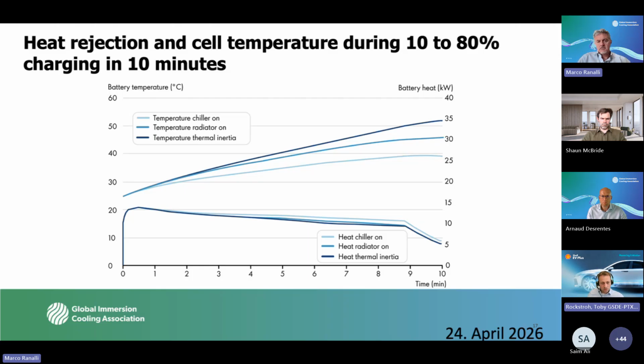Starting at 25 degrees centigrade battery temperature is very comfortable, so the thermal inertia of the system plays in our favor—we're able to absorb all the heat the battery cells generate in this coolant circuit, and we still maintain about 52-53 degrees centigrade even without any additional systems running.